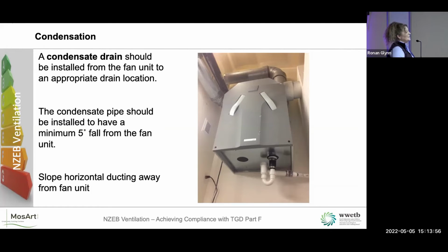People just don't do a simple thing like that, especially if you're doing your air permeability or blower door. Sometimes they close those valves off. So you have to make sure that they're turned back on again. So the condensate pipe should be installed to have a minimum of a 5 degree fall away from the fan. To be honest, you're lucky if they're there at all now, let alone have slope on it. Slope horizontal ducting away from the fan unit, obviously you don't want it ending up going back into the unit. So that's good.